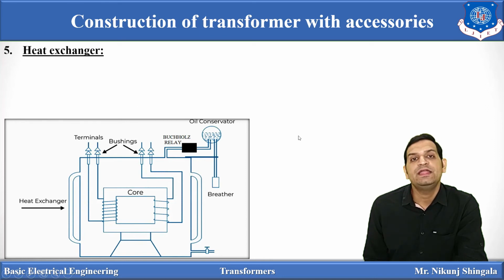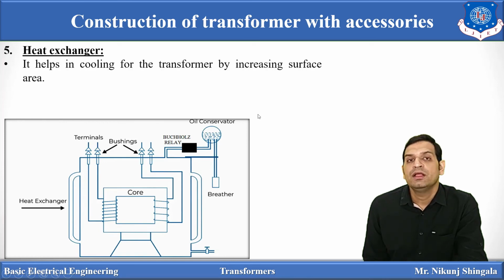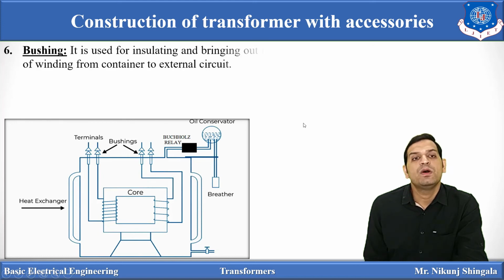Next one is the heat exchanger. As I told you, when supply is given, oil gets heated, so it should be cooled in a very short time. So heat exchangers or radiators are provided with the transformer tanks. Here you can see, this is nothing but the heat exchanger or radiator. Basically, it is provided with the transformer to provide cooling by increasing its surface area.